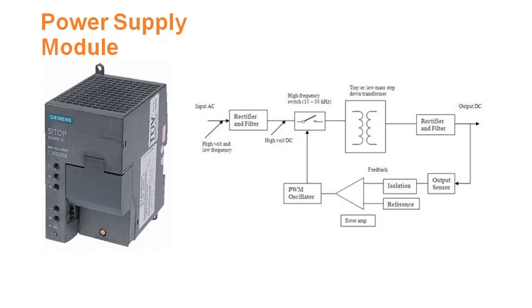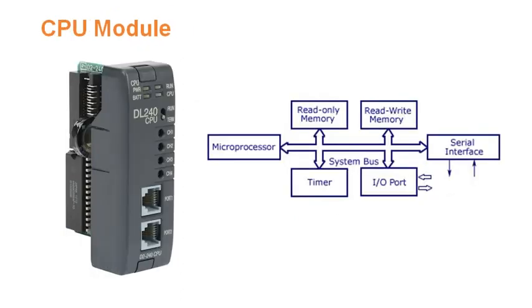The power supply module is the basic module of the PLC which takes the AC input and produces the DC output. The DC output ranges from 3.3 volts DC and 5 volts DC for the CPU, and 24 volts DC for the input and output module.